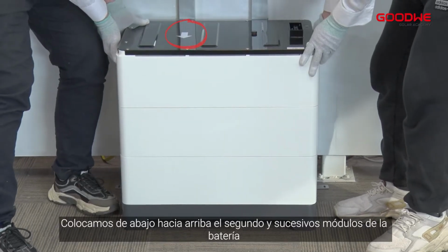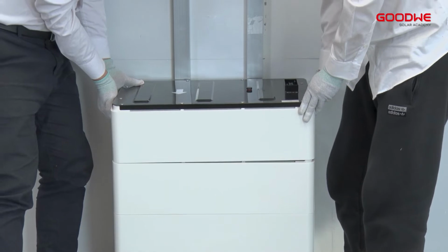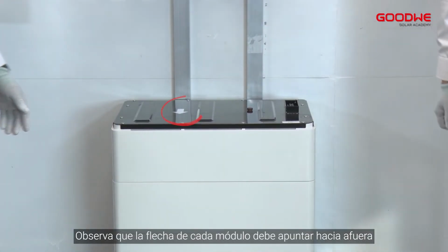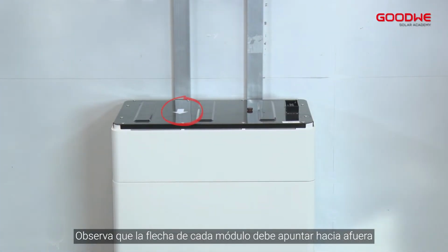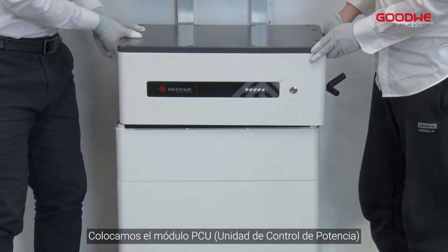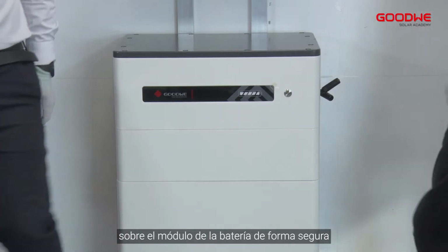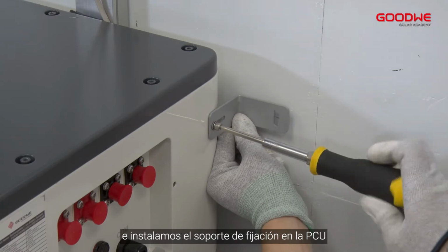Install the second to fourth battery modules from bottom to top. Please note the arrow on each battery module needs to point outwards. Put the PCU above the installed battery module securely, and install the locking bracket.